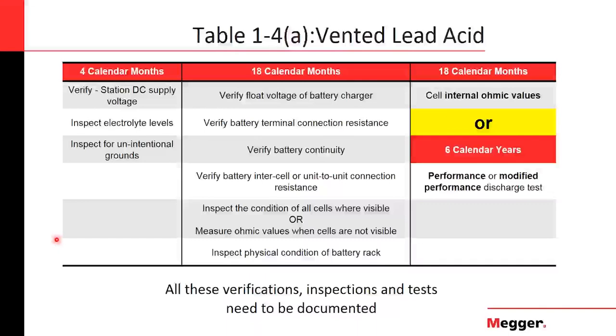Then every 18 calendar months, you again do a voltage verification of the float voltage of the battery charger. You also need to verify the battery terminal connection resistance, with a basic low resistance ohm meter or digital low resistance meter. Also, you need to verify that there's battery continuity. You want to be sure that the battery is not open or short-circuited. So a basic multimeter measurement as well can give you this value. It's just a confirmation that there's a circuit across the battery. And this is also confirmed with battery intercell or unit-to-unit connection resistance, basically a strap resistance measurement.